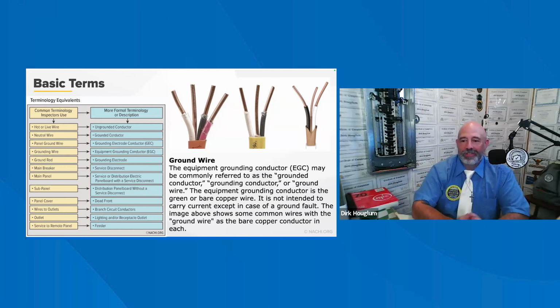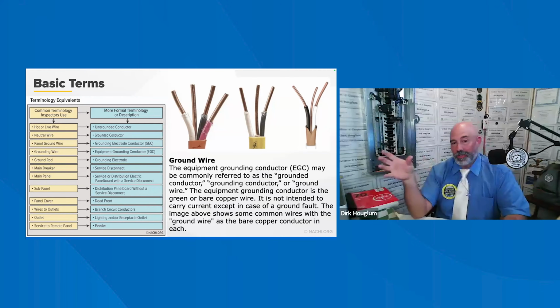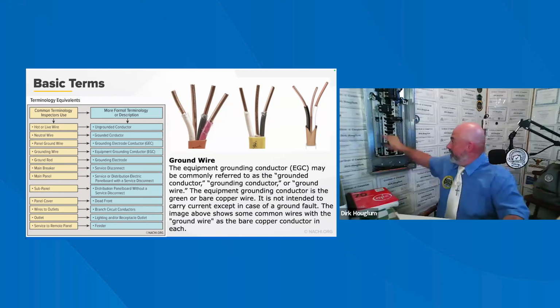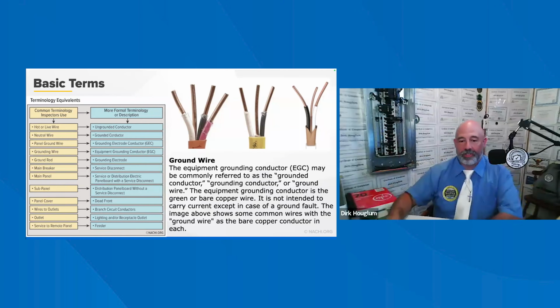Sorry. The grounded service conductor is what we call the neutral current-carrying conductor. Many inspectors refer to all grounded conductors, the white wires in the picture there, in all branch circuits as neutral conductors or neutrals, because they are all connected to the grounded neutral conductor in the service, so all the service panel. So if this is connected here, all my grounds would be here and my neutrals would be here. Because of this bar, they're actually connected together, and that's what that means. But if I disconnect it, the ground should be separate, and this would tell me that it's actually a subpanel, not a main panel. So that's kind of how that works.